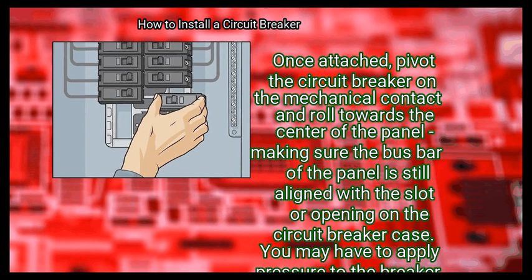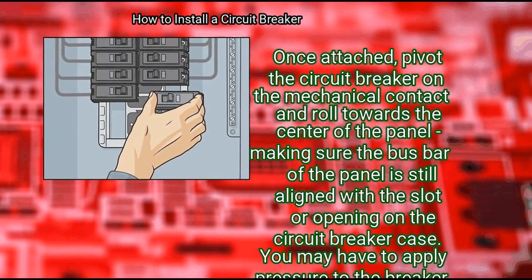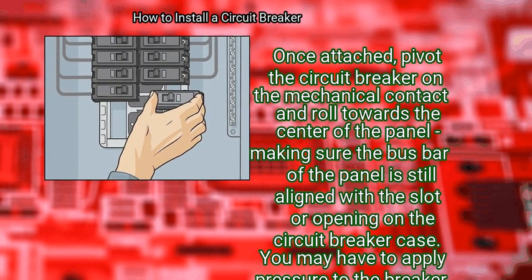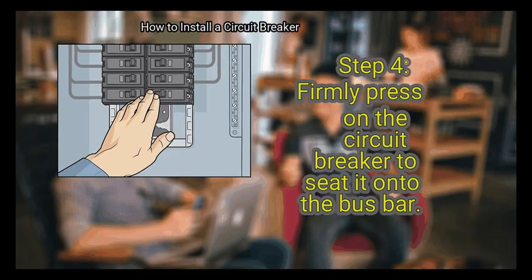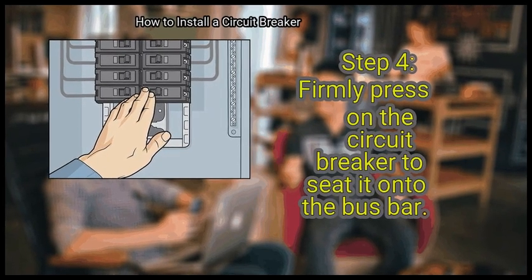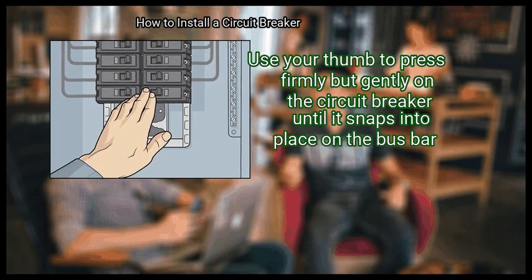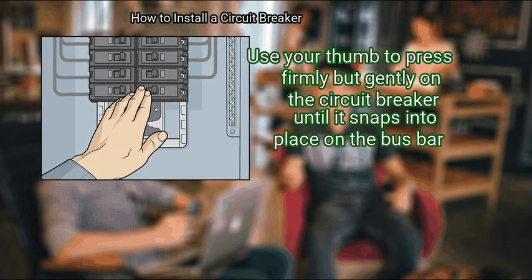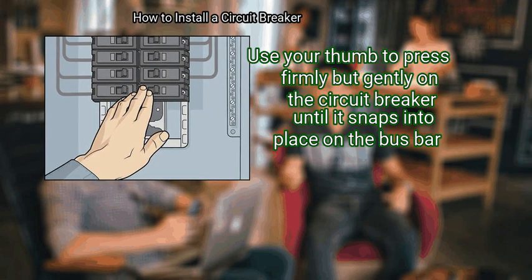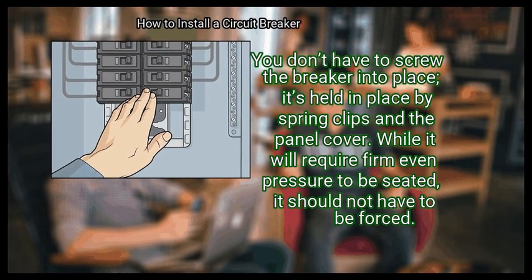Once attached, pivot the circuit breaker on the mechanical contact and roll towards the center of the panel, making sure the bus bar of the panel is still aligned with the slot or opening on the circuit breaker case. You may have to apply pressure to the breaker for it to become attached to the bus bar. Step 4. Firmly press on the circuit breaker to seat it onto the bus bar. Use your thumb to press firmly but gently on the circuit breaker until it snaps into place on the bus bar. You don't have to screw the breaker into place.